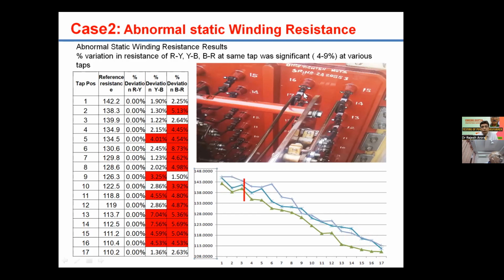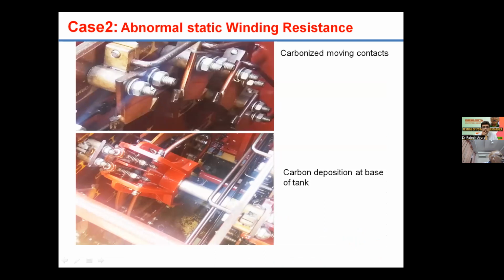One of the photos is attached here also. You can see here on these connections at the barrier plate some kind of carbon deposition, which you can see in almost all the taps. Further, in the last view of these moving contacts, you can see these contacts are also in a carbonized condition, and we found that a significant amount of carbon was deposited at the base of the tank also, maybe due to continuous arcing because of loose contacts. So these moving contacts were cleaned and tightness was ensured, and thereafter the transformer was taken back into service.